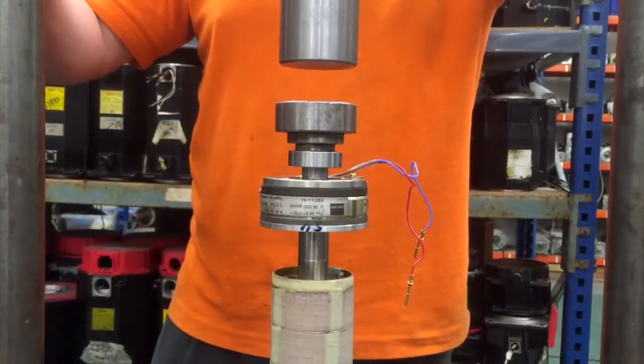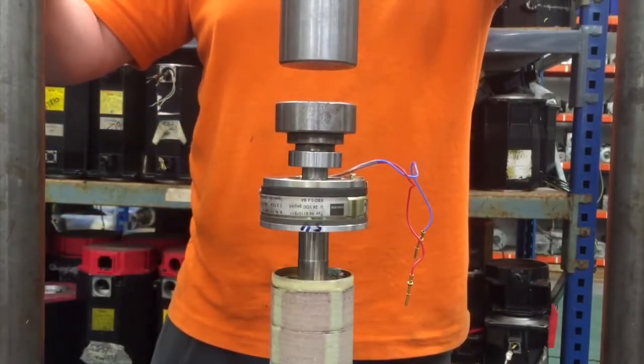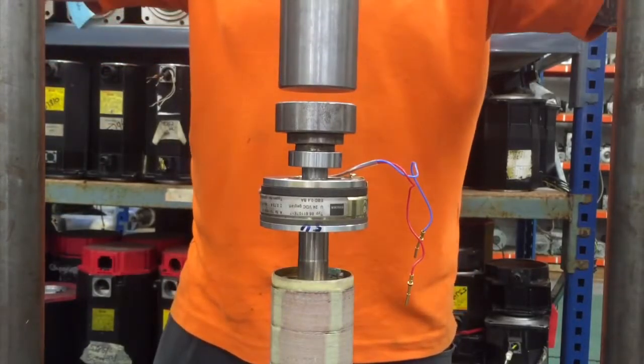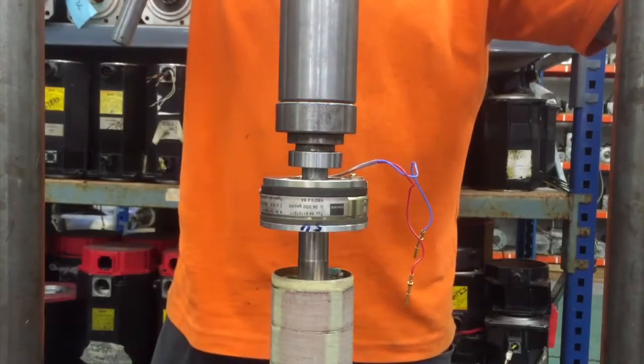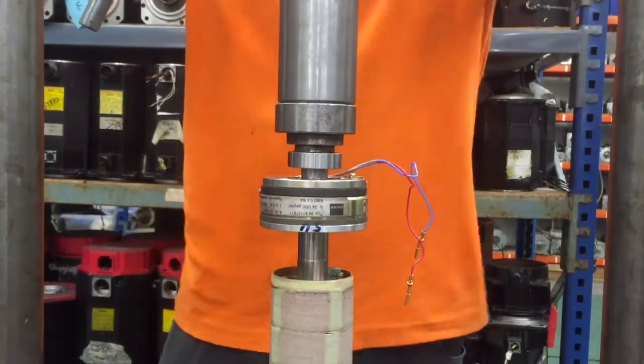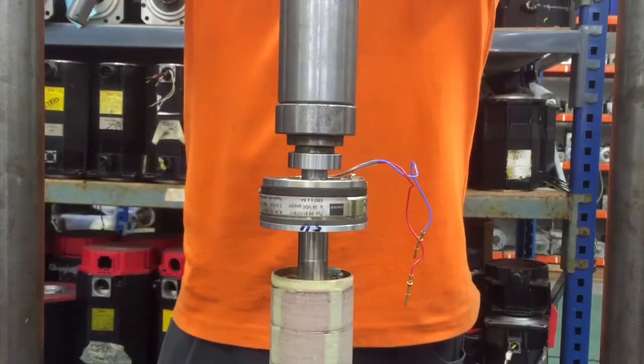The brake has now been located on the rotor shaft and now it is time to correctly fit the bearing. We use a cold pressing method with a fly press for this size bearing and the sleeve will push down over the inner race of the bearing and then locate against the bearing shoulder.